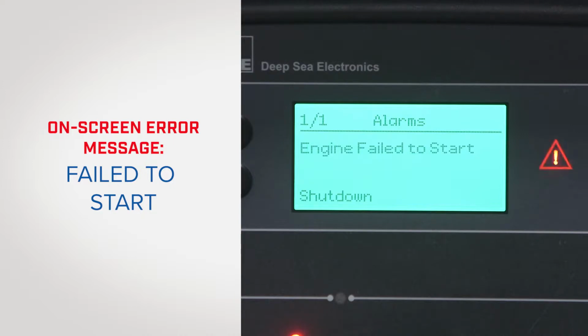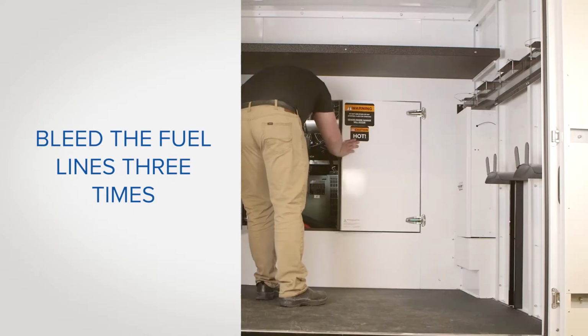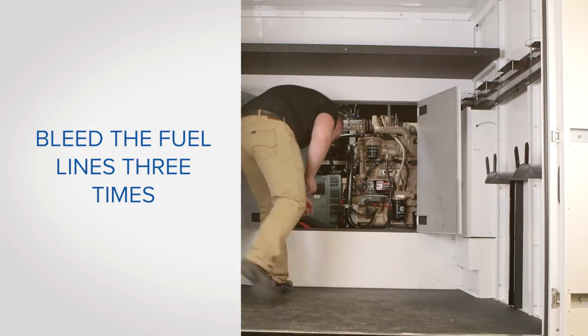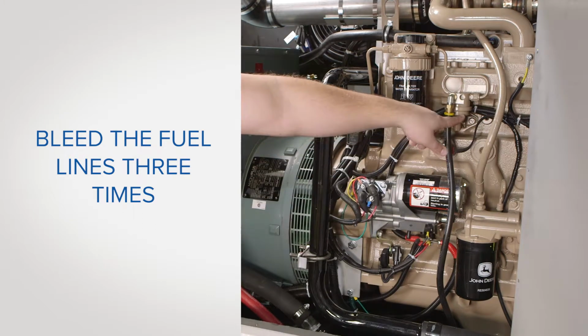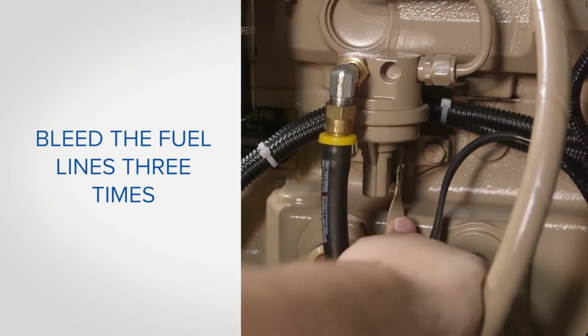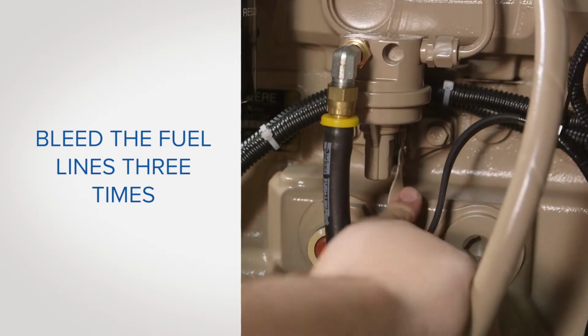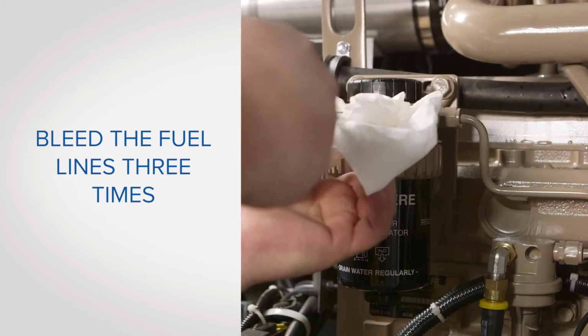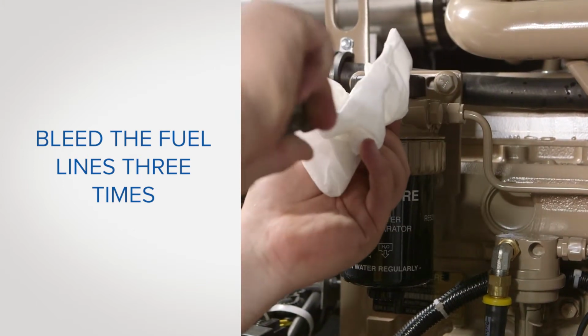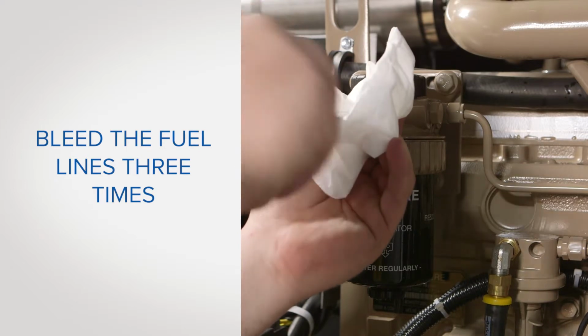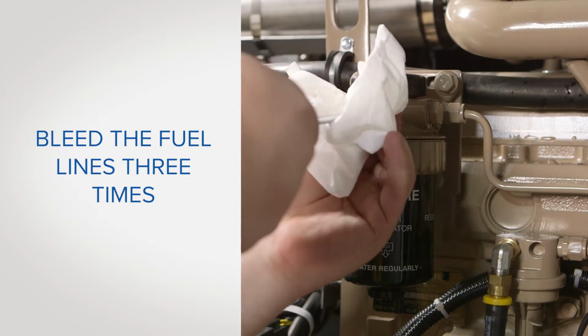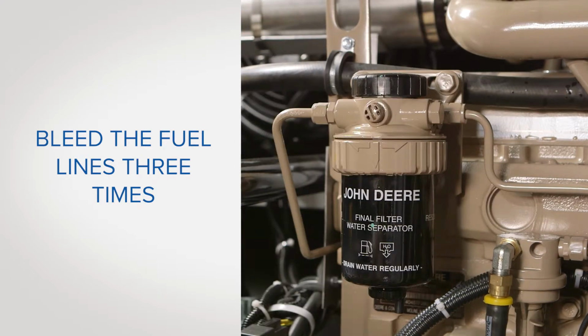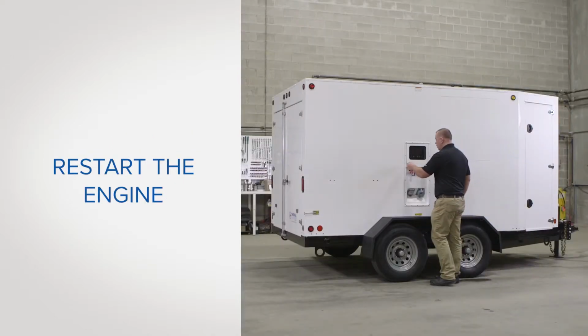If your control panel reads "failed to start," a common cause is the presence of air in the fuel lines. To resolve this condition, you will need to bleed the lines by using the manual fuel pump located next to the fuel filter. Pump 10 times, then open the bleeder screw located above the fuel filter. Repeat this procedure 3 times. Make sure you have rags available to clean up any fuel that leaks from the bleeder screw. Now, try to restart the engine.